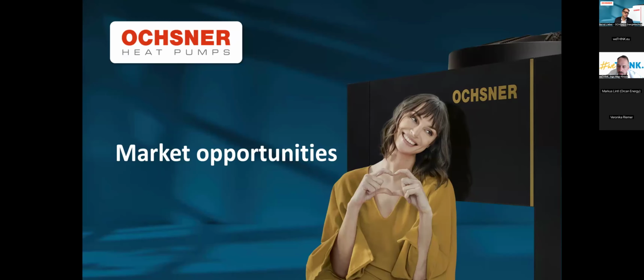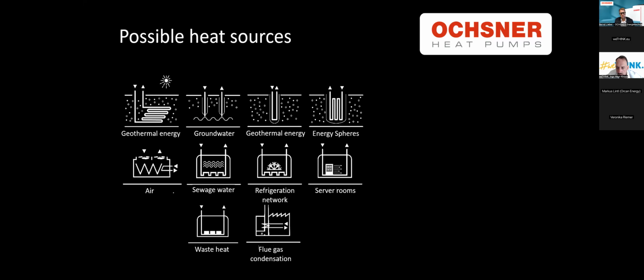For the market opportunities, it's also very important to have a deeper look, because many of you may know the standard air-to-water heat pumps or water-to-water heat pumps for the household. So the smaller sizes, up to 10, 20 kilowatt of heating capacity. Many of you may also know some larger capacities, also air-to-water, up to 100 kilowatts. But what we are talking about now, we are also going for new opportunities on the source side. So beside geothermal, groundwater and air-to-water heat pumps, we also use sewage water as a source for our heat pumps. We use waste heat, similar to the ORC process, out of the chimney of biomass plants. We use this as flue gas condensation in this case.